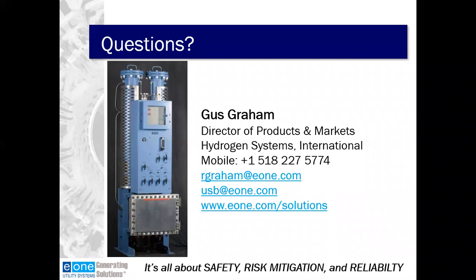Well, if it's referring to a leak of water in the generator, again, the regeneration process is occurring concurrently with the tower being in service, so it'll continually be drying the generator. If they're referring to a leak of water into the generator, we'll be able to remove that water, up to a certain point depending on how big the leak is, because the regeneration process doesn't stop the drying process. We have the two towers for that reason. One is always in service by design. The second one is in maintenance. Okay, so if we were performing maintenance on the gas dryer while the generator's online, and you sprung a water leak, a clip leak, and the dew point started rising in the generator, obviously it's cause for concern.